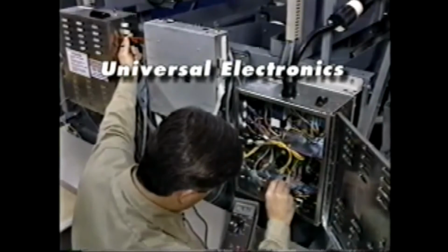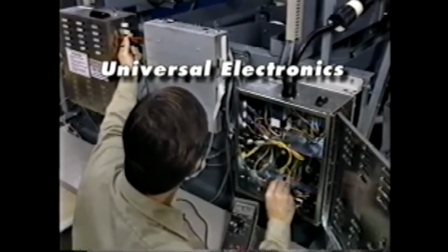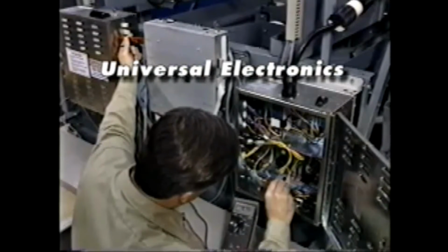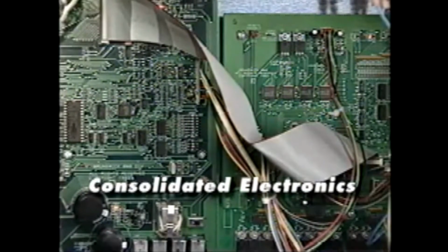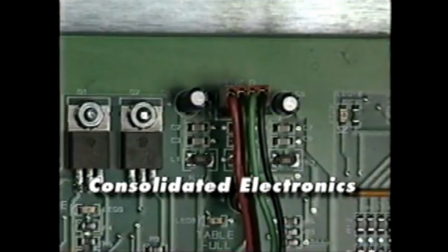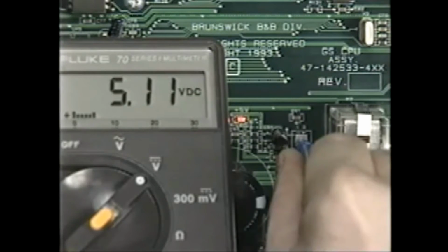Quarterly maintenance. On universal electronics, check the 5-volt adjustment at J5 on the universal game setter box and adjust at the common box if necessary. On consolidated electronics, check the 5-volt adjustment at J1 on the consolidated low-voltage I/O board. Adjust this at the CPU board if necessary.